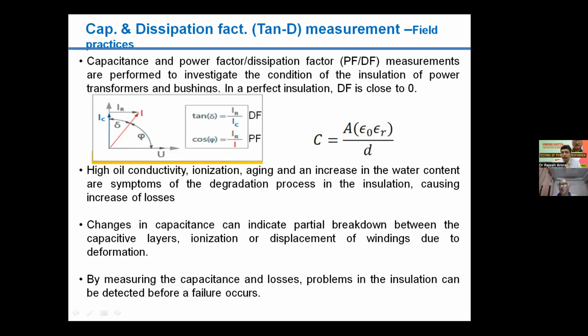Changes in the capacitance can also indicate partial breakdown or some issues related to the insulation, and even some deformation that has taken place, because as we see from the formula itself, capacitance is equal to epsilon A by D. So if there is a change inside the geometry of the winding, or some displacement has taken place, then again by measurement of the capacitances, this kind of information may be drawn, whether the transformer is healthy or some issues are there with the transformer.